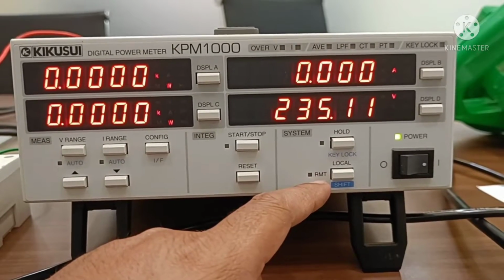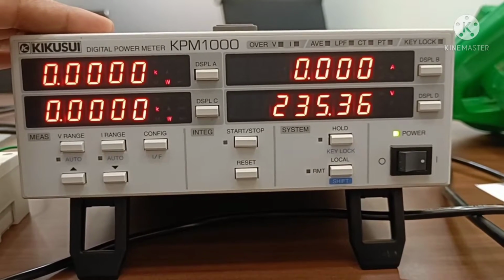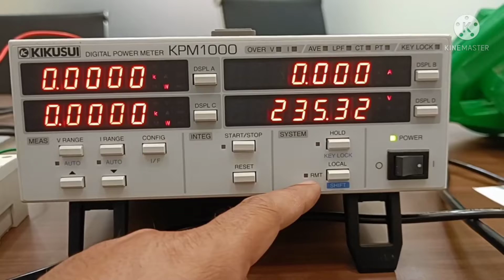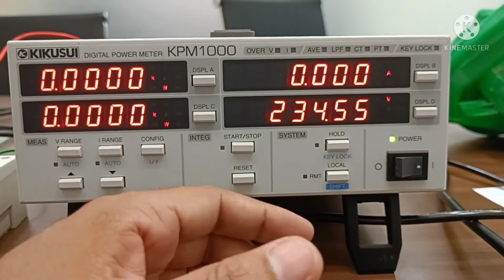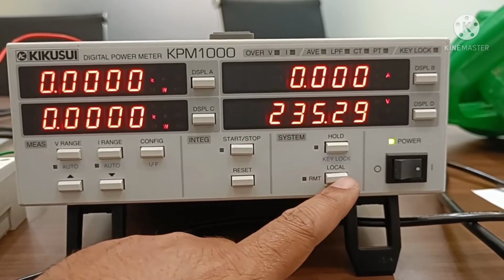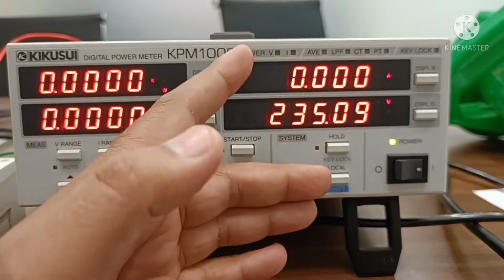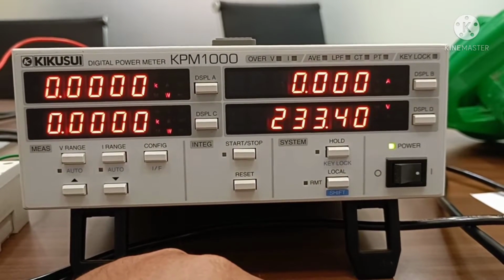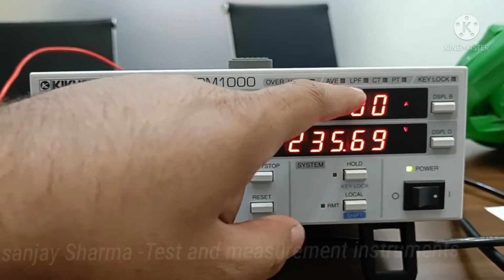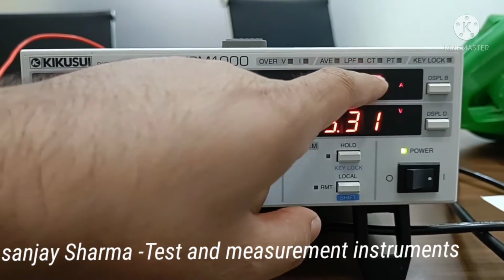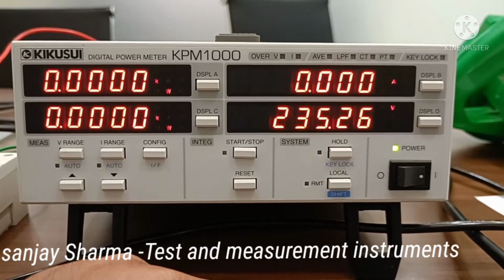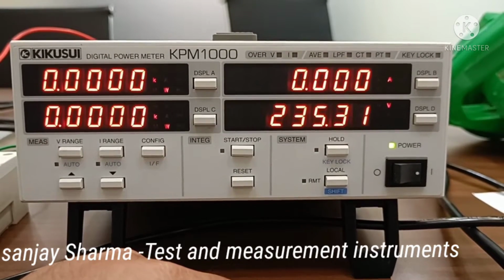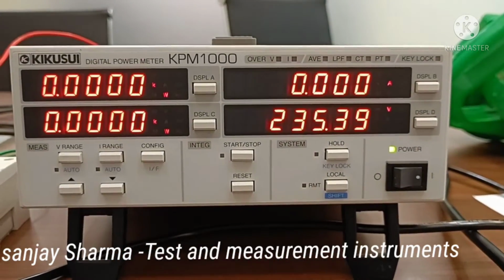This is the remote setting. When the power meter is connected with the system, the remote indication will start glowing, which means you cannot change anything from the instrument itself. By pressing the local switch you can disconnect the system and the power meter, and after that you can change whatever you need. You can also add digital indications like over voltage, current, average, low pass filter, CT, PT. CT means current transformer, and PT means potential transformer, used to increase the input voltage capacity to measure power consumption in electronic devices. Okay, so I'll make some wiring.